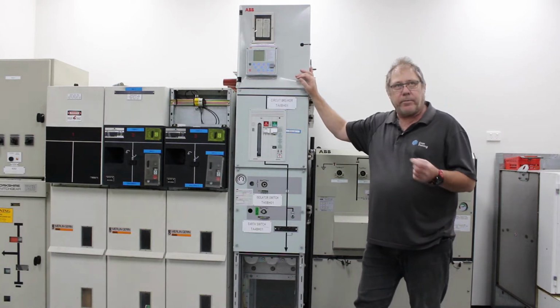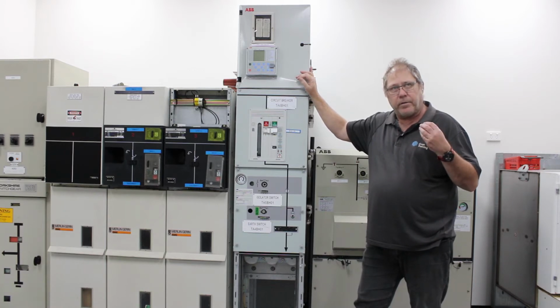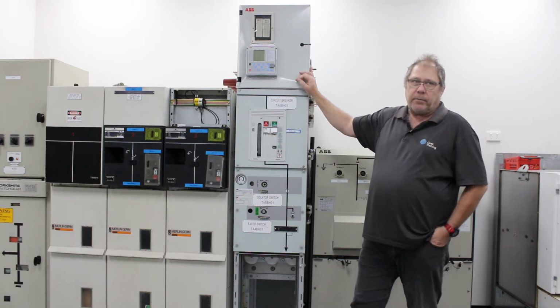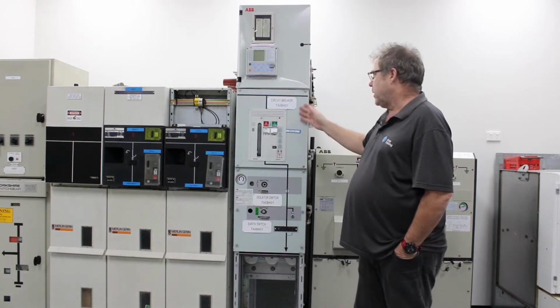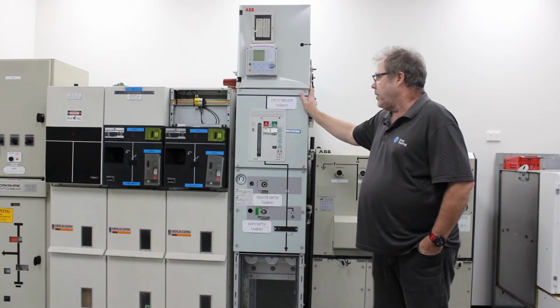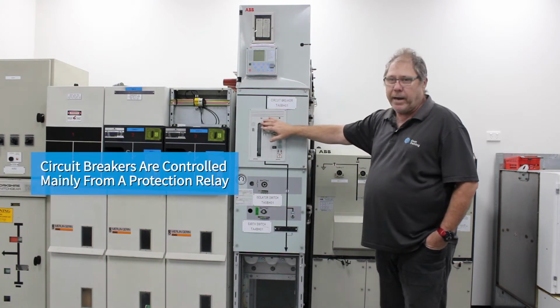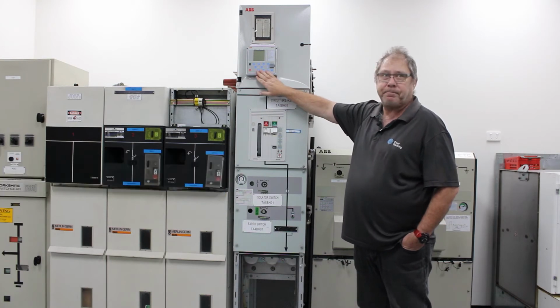Primarily, the miniature circuit breakers in your switchboard at home are all self-contained, and the trip curves of those circuit breakers are predetermined. When you start dealing with high voltage systems, such as circuit breakers like this, the circuit breakers are controlled mainly from a protection relay.